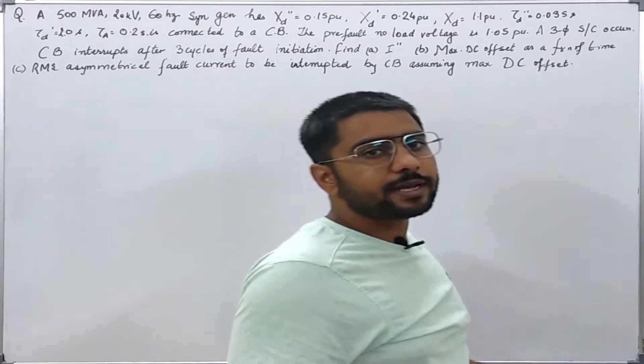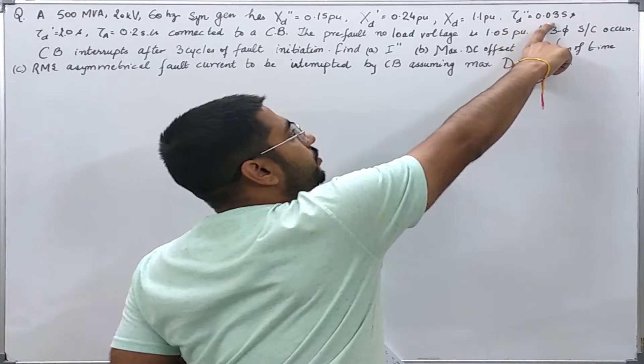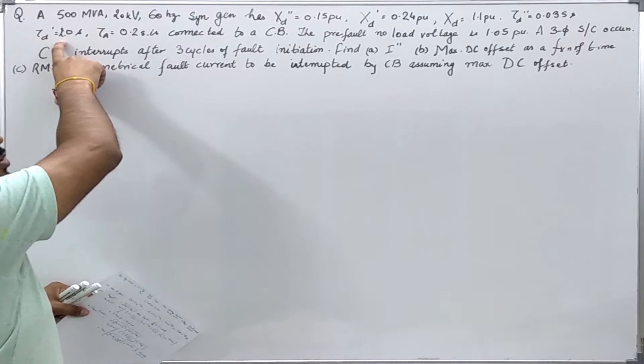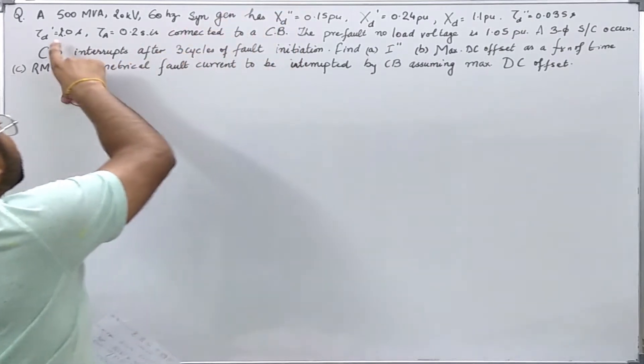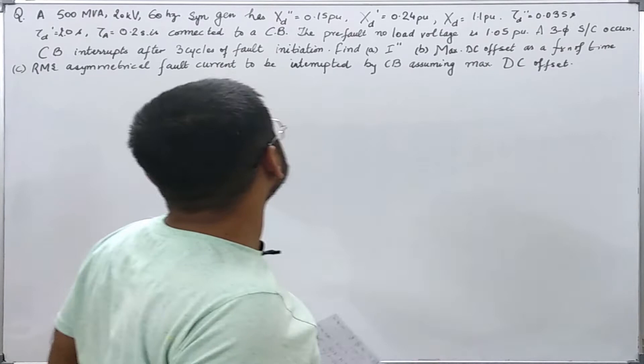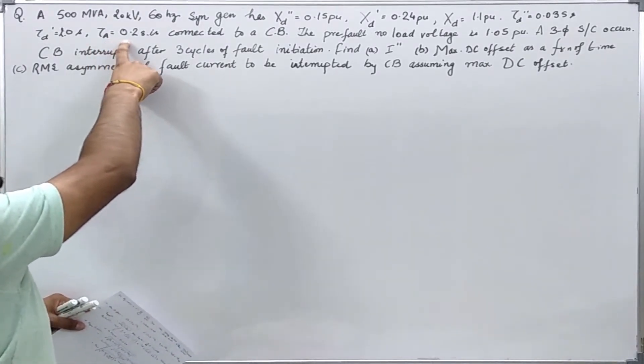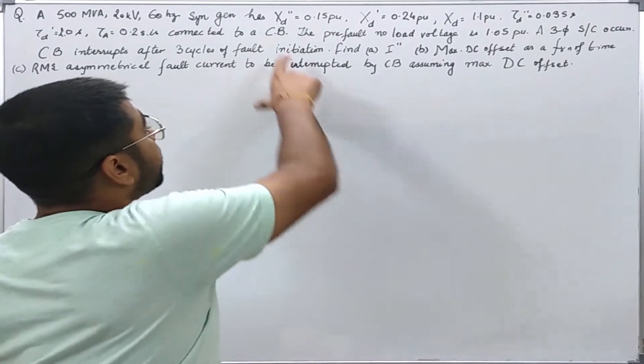We are also given various time constants. The sub-transient time constant is 0.035 seconds, the transient one is 2 seconds. You can see the difference - this is very small compared to the transient time constant because it depends upon the field winding which is highly inductive, and it depends upon the damper winding and the eddy currents. The armature winding is having a time constant of 0.2 seconds and this generator is connected to a circuit breaker.